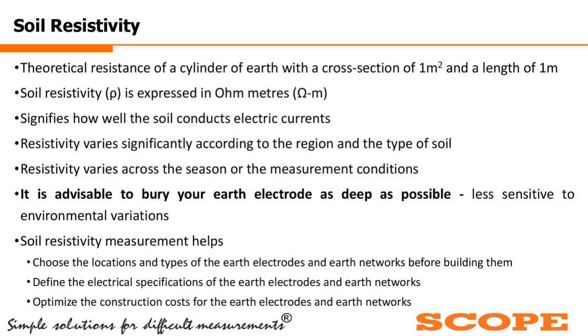Also, there are other things like stray voltages or stray currents available on the earth's surface. If there are stray voltages and stray currents on the earth's surface, the value of earth resistance or earth resistivity will change. But when we go deeper into the soil, these superficial values, the stray voltages and stray currents on the surface, go to their minimal values. Hence, we mention here that there is less sensitivity to environmental variations when the electrode rod has gone deeper.